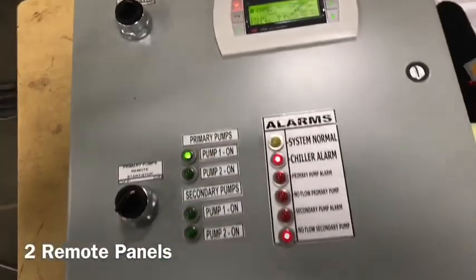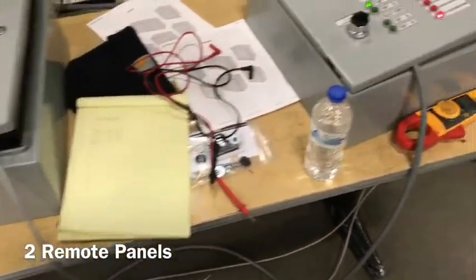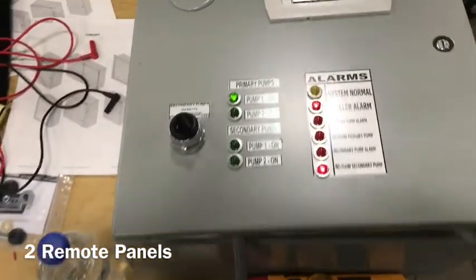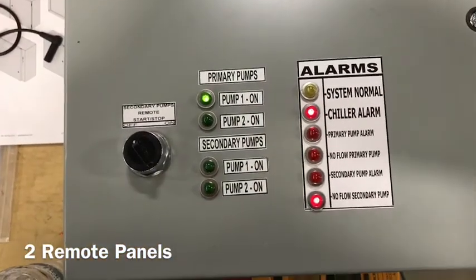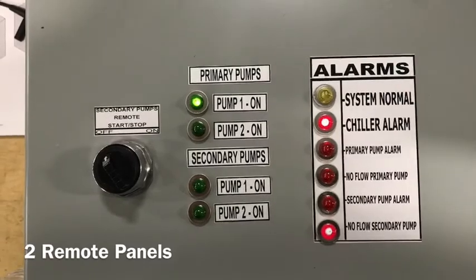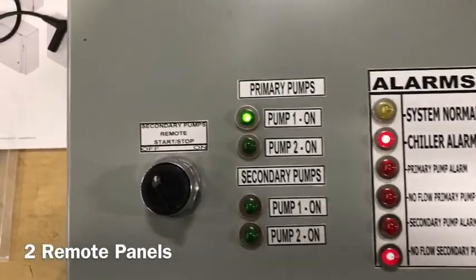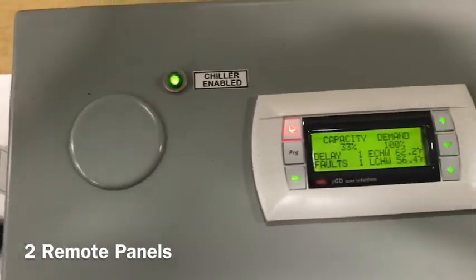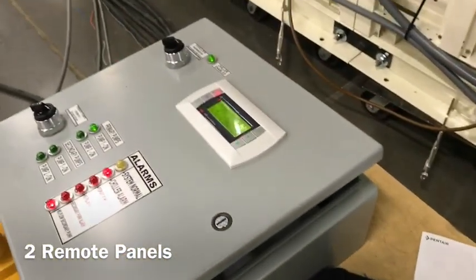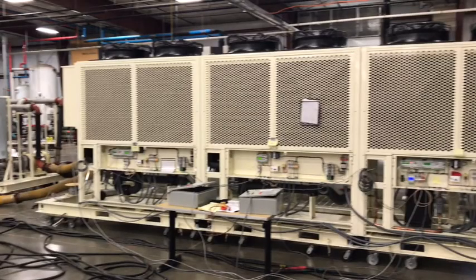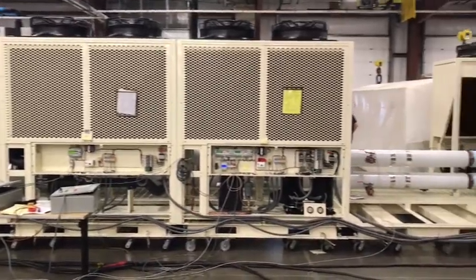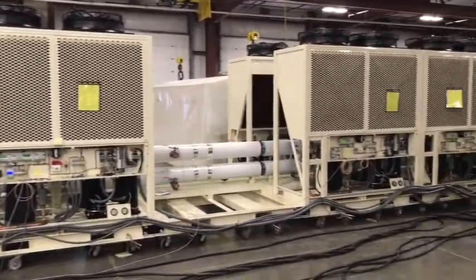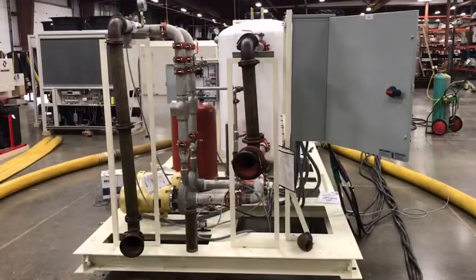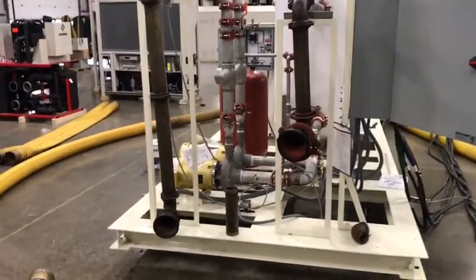When we go over to the other remote panel, you'll notice it's identical except that it does not have a chiller start stop. So indicator lights on the right, the barrel switch is the start stop for the other set of pumps. There are two sets of pumps on this project, a primary loop and a secondary loop. And that fill-in section is in the spot where a chiller start-stop would normally be, but we can really only have one chiller start-stop. We'll continue on panning to the right with the free cooling modules and then the mechanical modules at this end of the machine. And we'll continue on with our tour of the pump module.